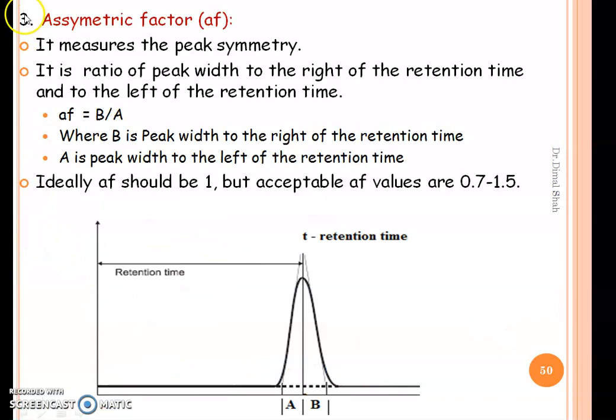The third parameter is asymmetric factor, which measures peak symmetry. It is the ratio of peak width to the right of the retention time (B) to peak width to the left of the retention time (A), so AF = B/A. Ideally, for a symmetric peak, the asymmetric factor would be 1, but acceptable values are 0.7 to 1.5.